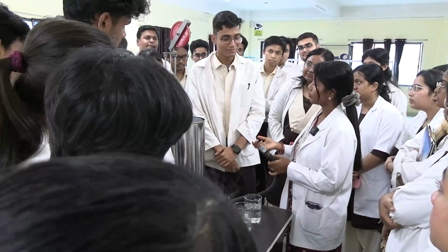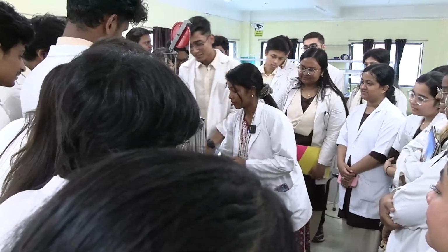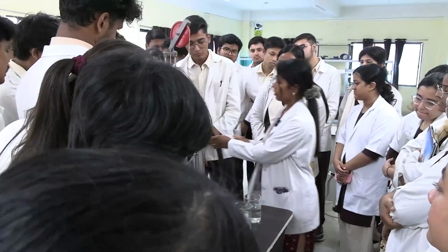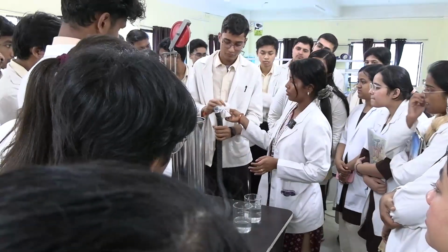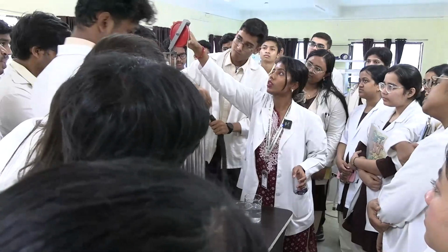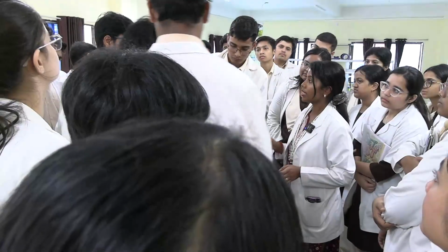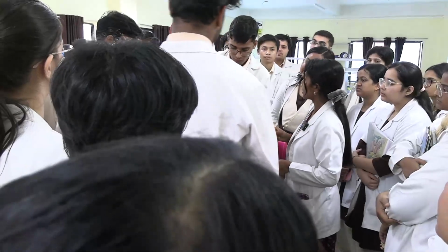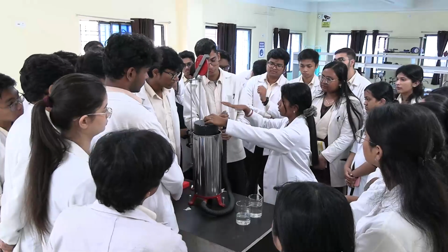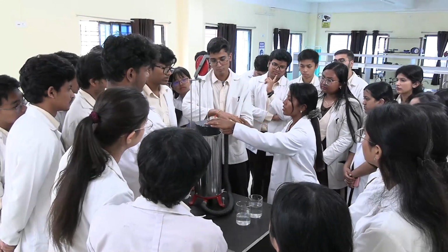Do you have your hanky? So hold it. Before doing, the pointer should be at 0 always, and it should be flat. You have to check first whether there is any leakage or not. So how are you going to check that? Close it. It's not going down, right?